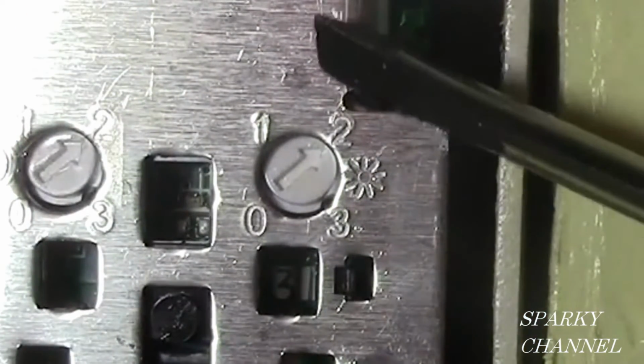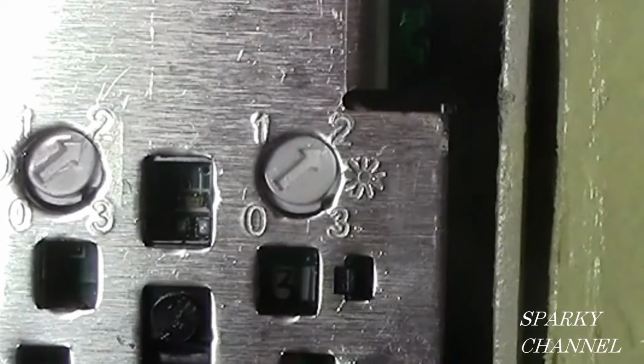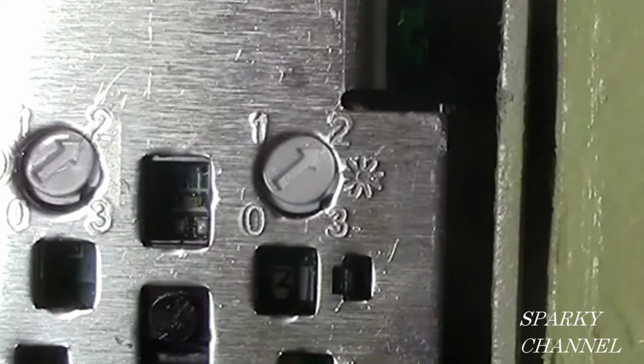If you put it on 1, it will come on with the most amount of darkness. In other words, it's much more sensitive if you put it at number 3. The 0 setting on the right side is the vacancy sensor setting. If you set it to that setting, you must then turn on your light manually. You have to turn the switch on manually, and then it will go off after people have left the room in the prescribed amount of time that you have told it to on the left-hand dial.